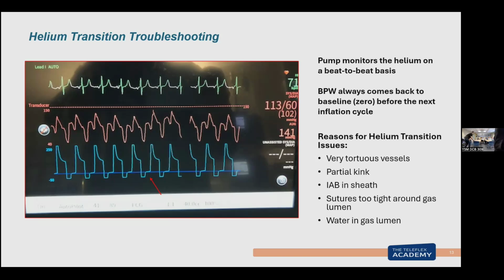And then the other thing we have to watch out for is condensation in the tubing. Our pump drains the condensation out and puts it in a little bottle so it doesn't get in the line. But if you ever saw condensation in the tubing, that will slow the ability for helium to get in and out, so I would watch for condensation. Our pump should not have condensation in the tubing. If it does, the staff didn't check the condensation bottle and empty it, or I've got an issue with that pump in removing the condensation, and then I would switch out that pump because our pump is supposed to keep that area dry.